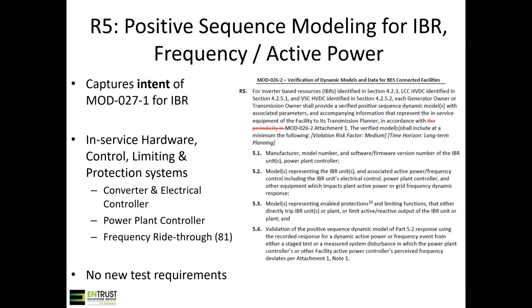Really, this R5 is focusing on your frequency bias, right? That's a synthetic feature for inverter-based resources because they don't truly have a speed. There's no mechanical system like there is for synchronous machines. But we know from FERC Order 842 that pretty much any new site has to have frequency bias. This is a required feature for the grid to operate coherently, to have contribution from all its resources.